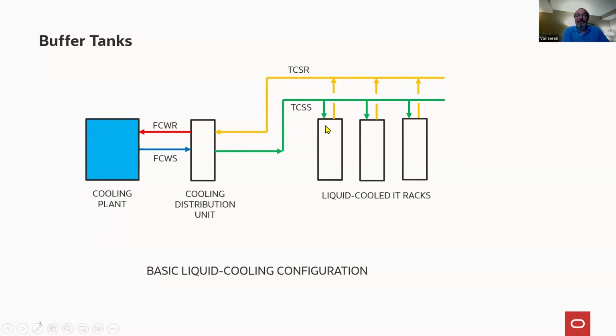Yeah, okay. So we've got the liquid cooled IT racks in a loop that's fed from a cooling distribution unit. Basically, the cooling distribution unit has onboard pumps that pump the technology cooling system water into the racks, and I'm calling this TCS supply, technology cooling system. It goes into the racks, goes right down to the chip level. The TCS water picks up the heat, gets returned back, comes back hot, and on the other side of this heat exchanger, I have the chiller plant, which is putting out chilled water, and we're calling it facility cooling water, and I'm designating facility cooling water supply. So this is the cold water, and it picks up the heat from this heat exchanger and returns it back to the chiller plant, cooling plant, whatever the system is at back of house to be able to reject the heat to the outside. So this is just a very basic view of that configuration.